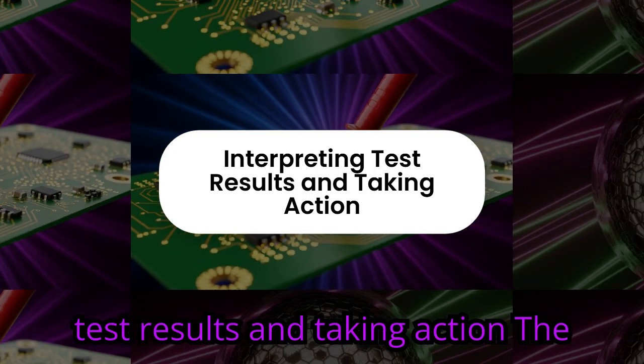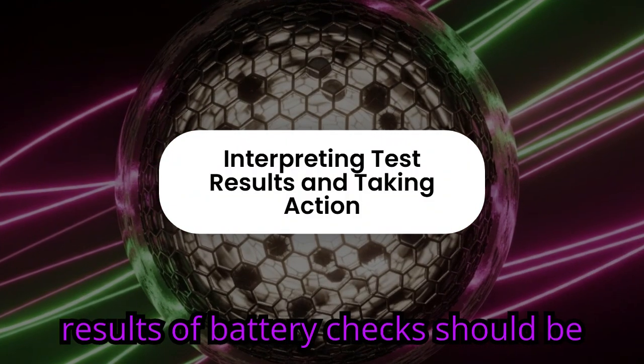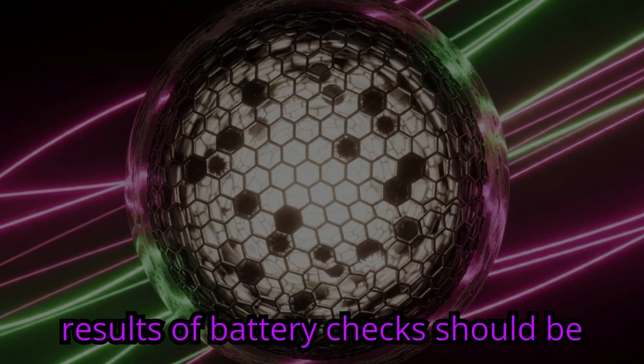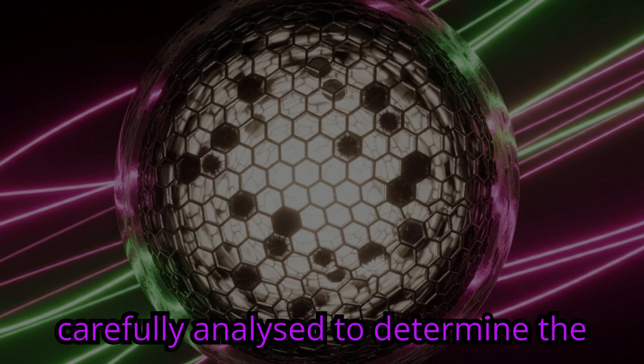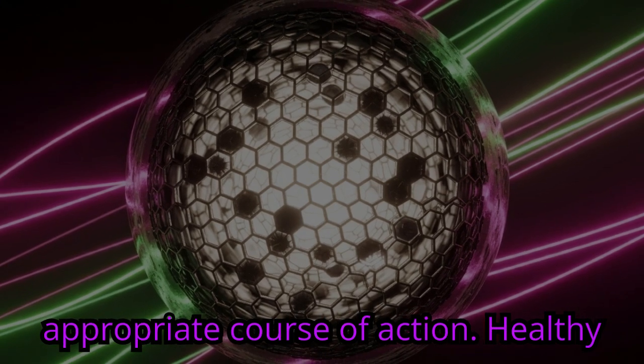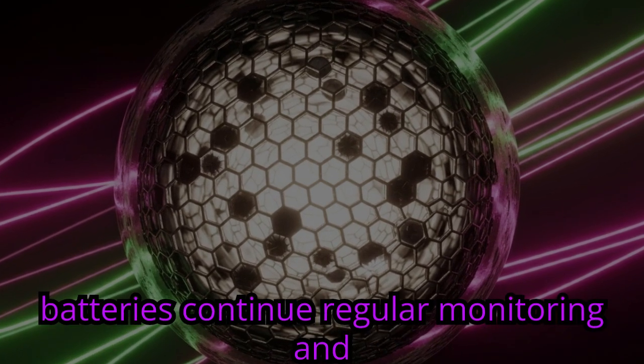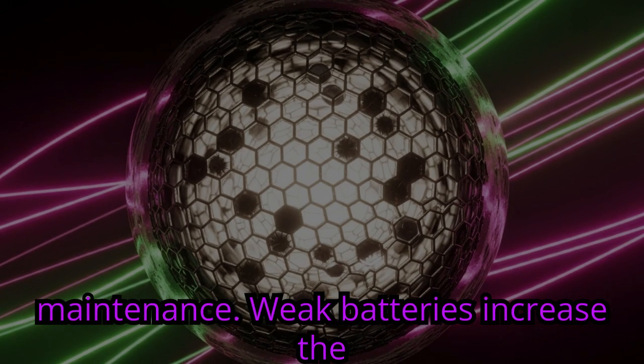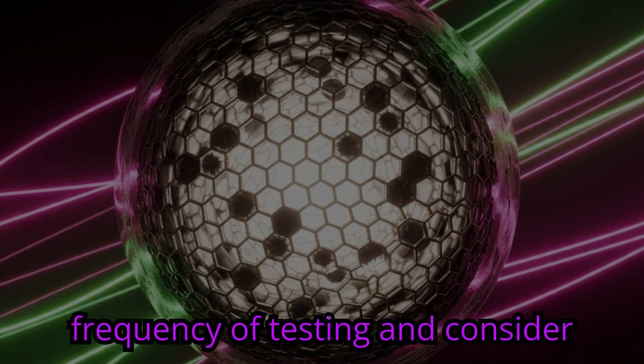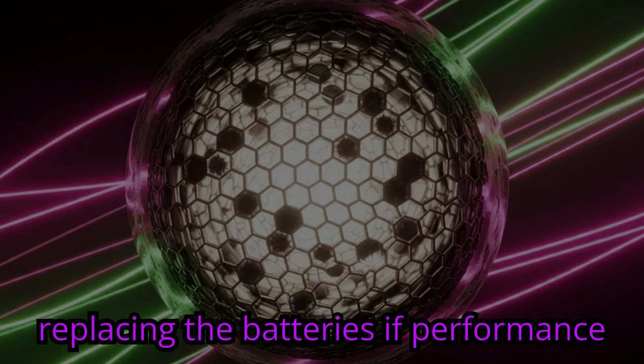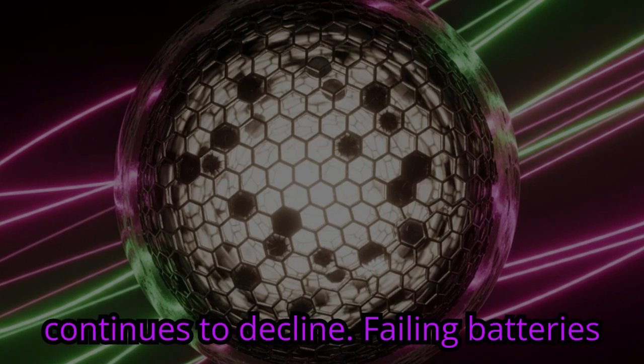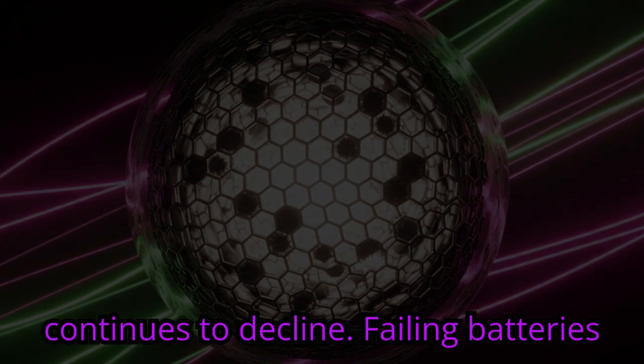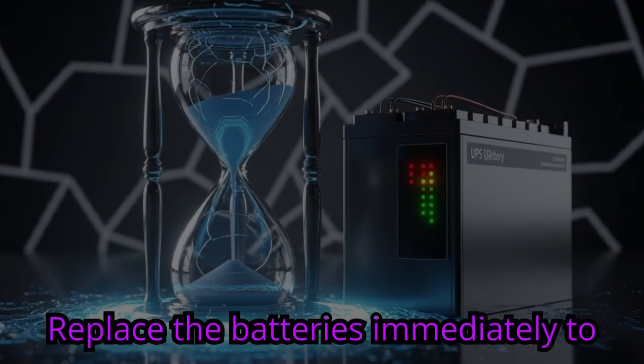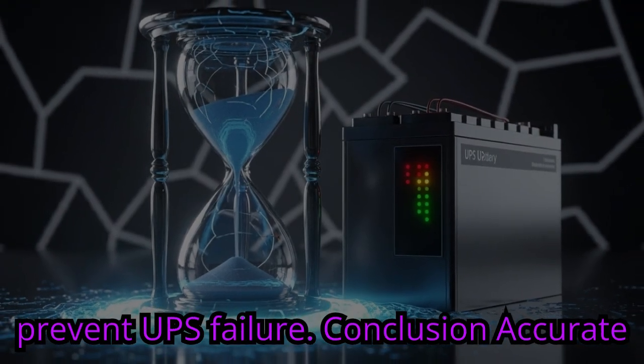Interpreting test results and taking action. The results of battery checks should be carefully analyzed to determine the appropriate course of action. Healthy batteries. Continue regular monitoring and maintenance. Weak batteries. Increase the frequency of testing and consider replacing the batteries if performance continues to decline. Failing batteries. Replace the batteries immediately to prevent UPS failure.